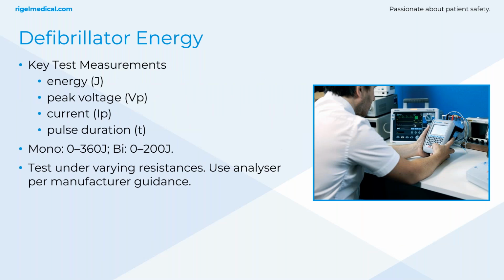What are the key test measurements? One is the amount of energy. We want to make sure that the total amount of energy delivered during a shock is what it's specified to, and there are specifications for that. They go up to 360 joules for monophasic, and then biphasic 200 joules, although the monophasic defibs are typically being phased out in more modern models, and biphasic is more commonly used.